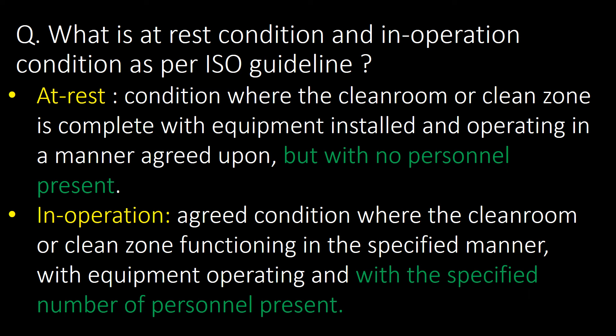What is the at-rest condition and in-operation condition as per ISO guideline? The at-rest condition is the condition where the cleanroom or clean zone is complete with equipment installed and operating in a manner agreed upon, but with no personnel present. The in-operation condition is the agreed condition where the cleanroom or clean zone is functioning in the specified manner with equipment operating and with the specified number of personnel present.